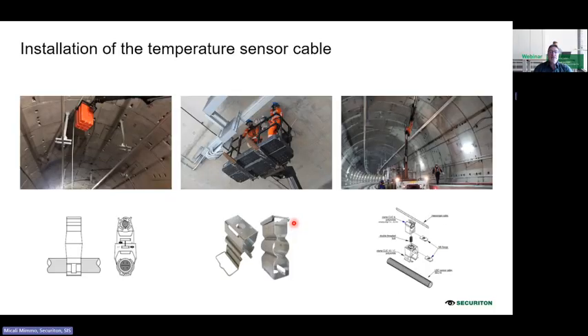The installation of the sensor cable is very easy. It sometimes depends a little bit on the roof. If you have a regular roof or an irregular roof, you choose the right support accessories. And normally, as I said, the fire detection system is always one of the last systems to be installed, so it's actually very fast. If you have good access, you first install all the clips and then you come behind and install the cable.